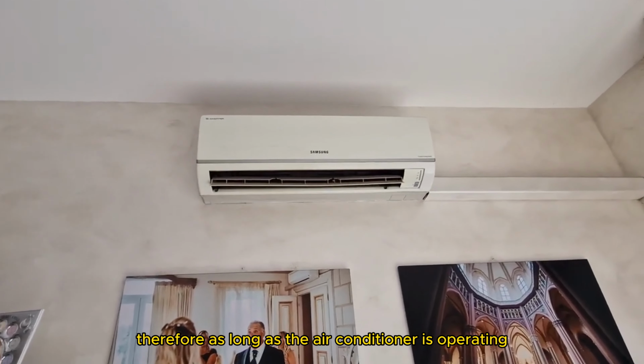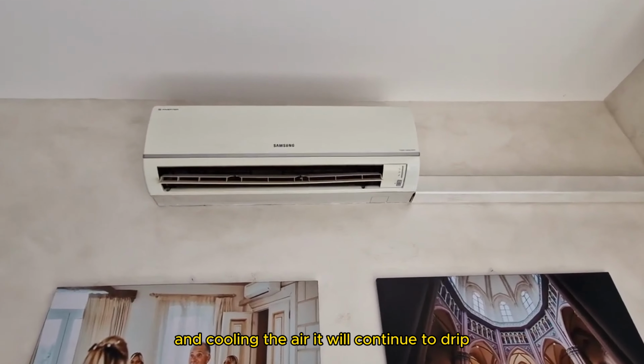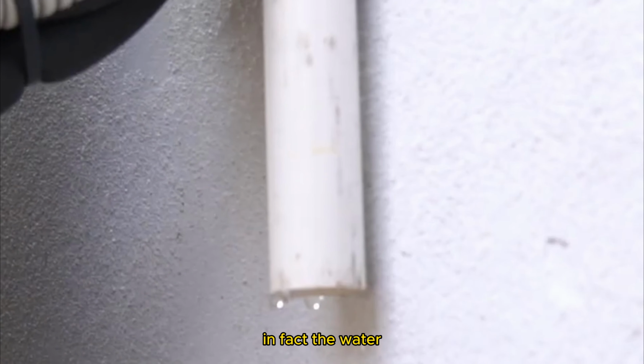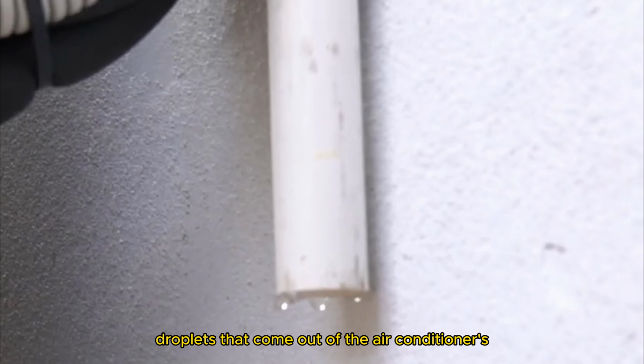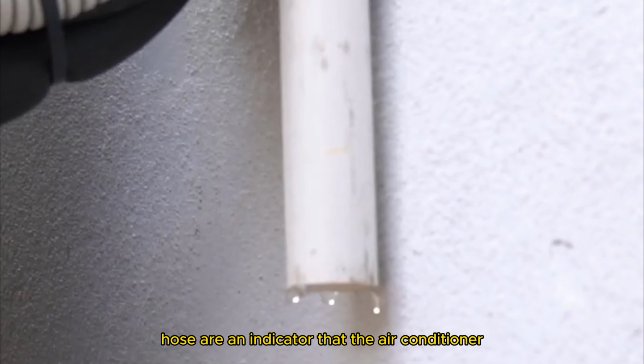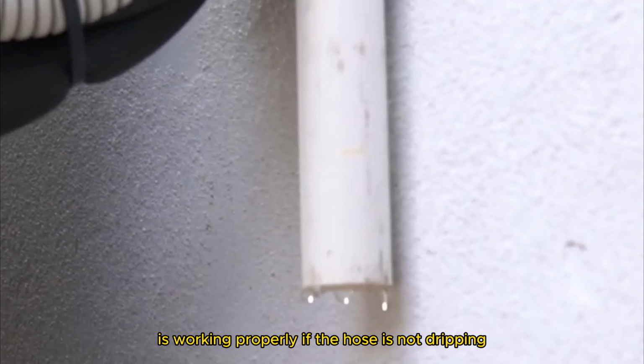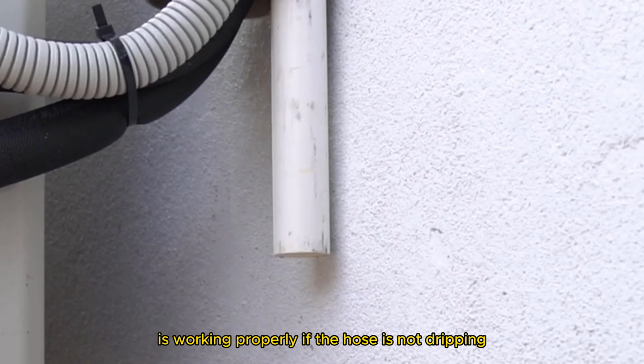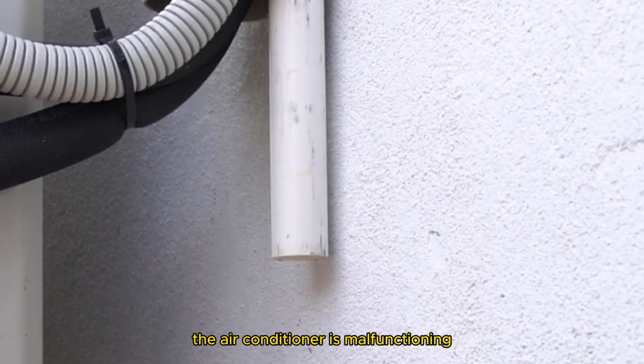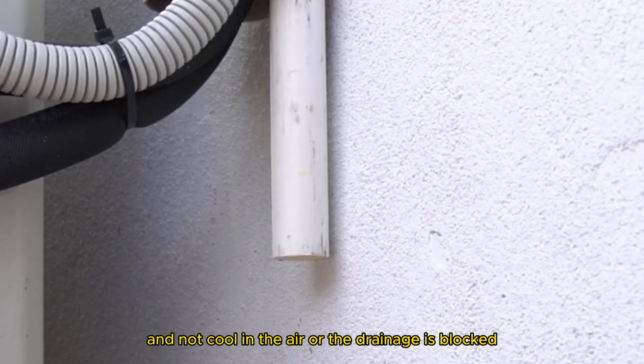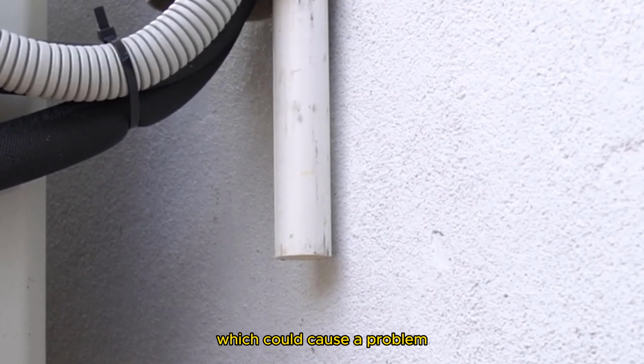Therefore, as long as the air conditioner is operating and cooling the air, it will continue to drip. In fact, the water droplets that come out of the air conditioner's hose are an indicator that the air conditioner is working properly. If the hose is not dripping, it means that either the air conditioner is malfunctioning and not cooling the air, or the drainage is blocked, which could cause a problem.